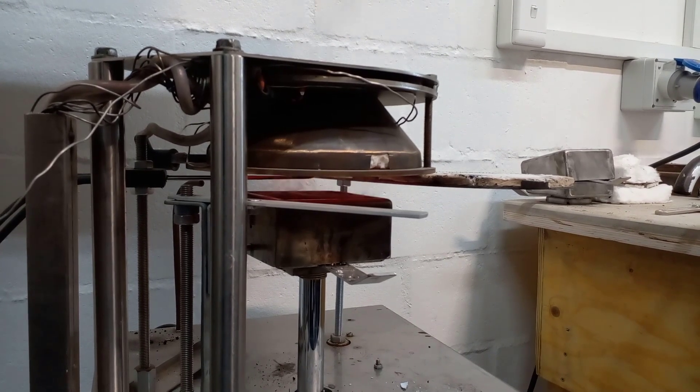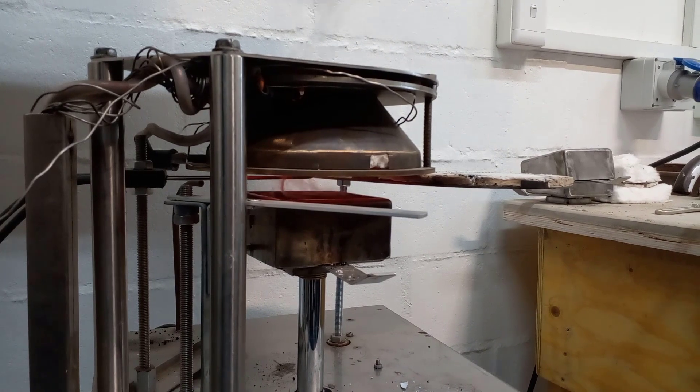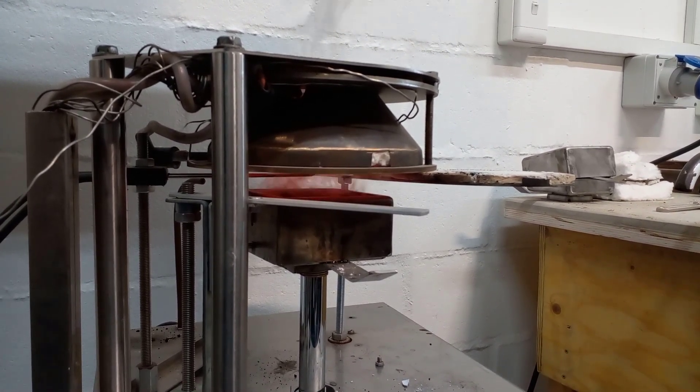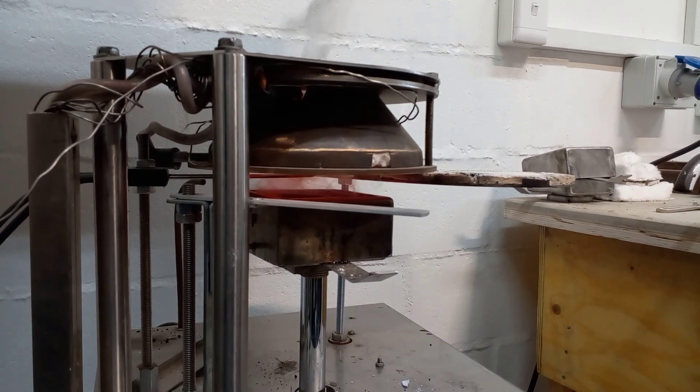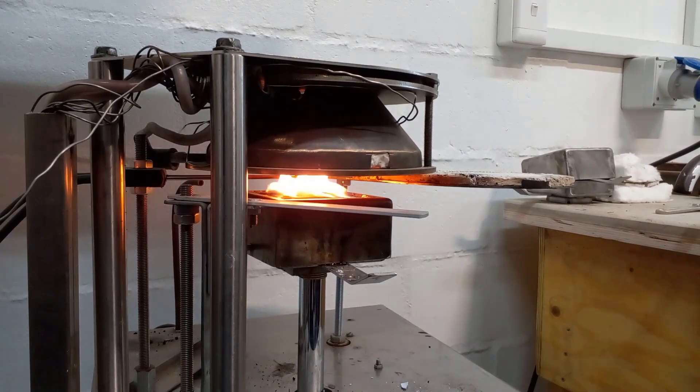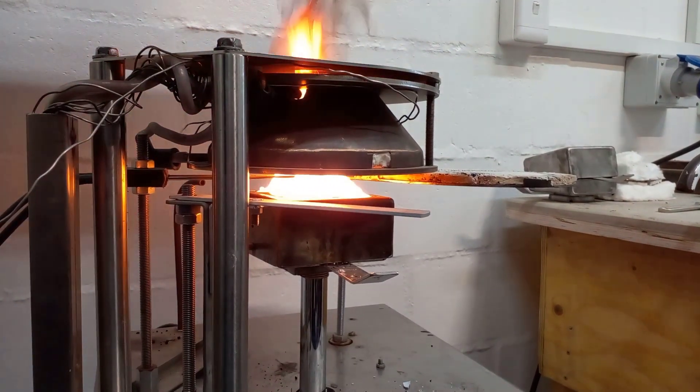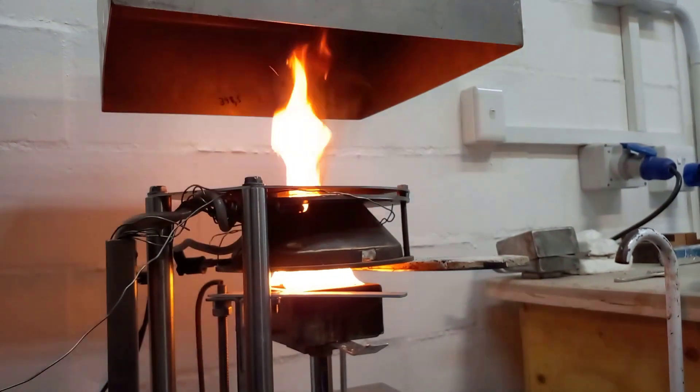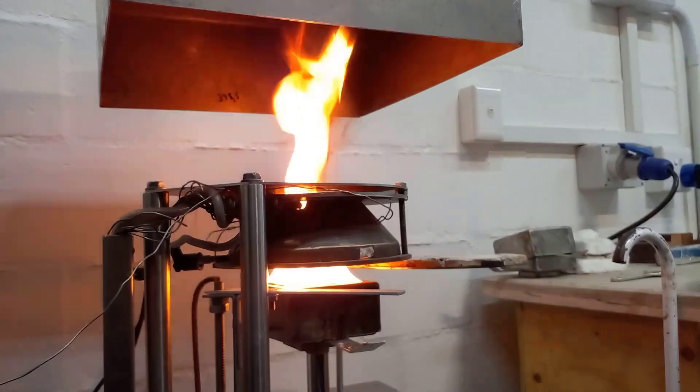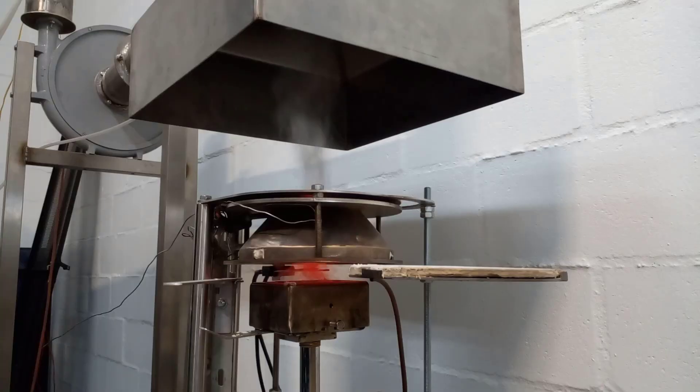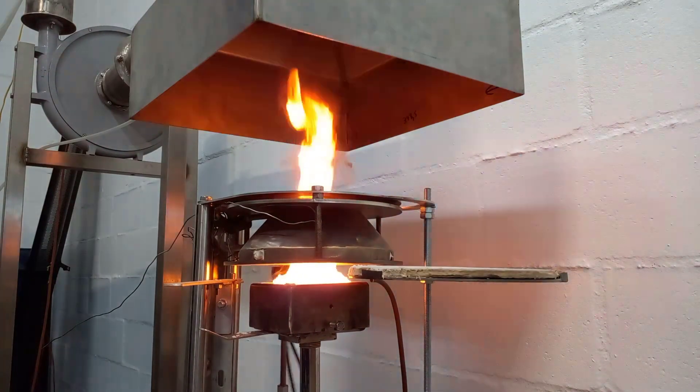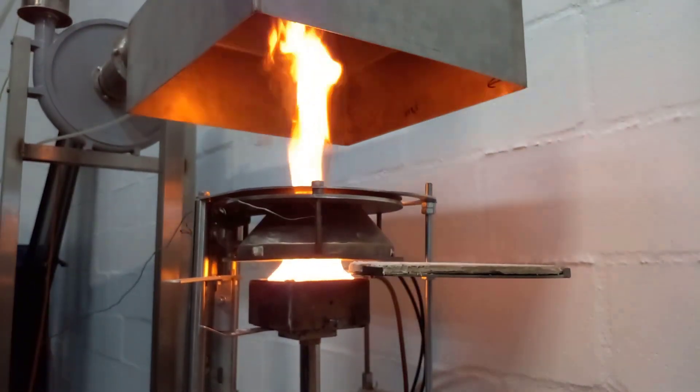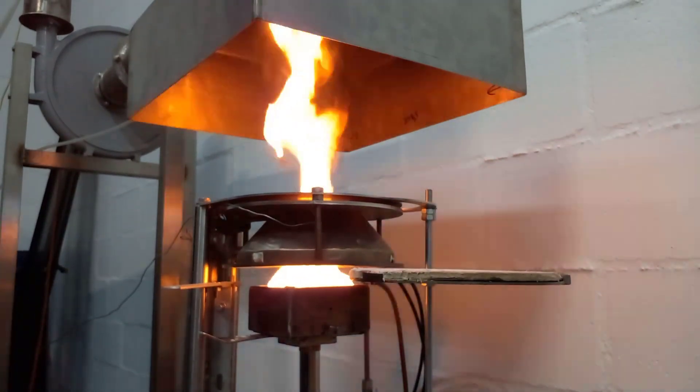The sample is now subjected to the flux for a period of time. Depending on the material, it may be very quick to ignition or take a while. There's an igniter just above the sample that's constantly flashing to provide the spark needed. The pyrolysis gases coming off the material eventually get to a concentration where they can ignite, and then once it's ignited, the material burns with all the gases going up the chimney.